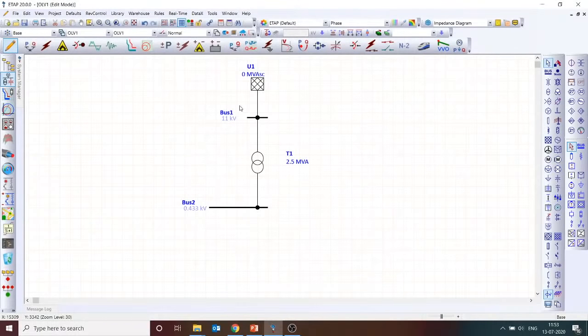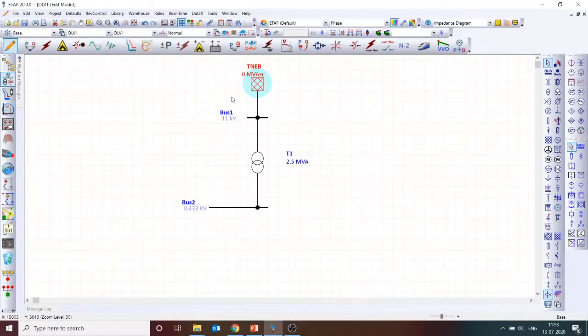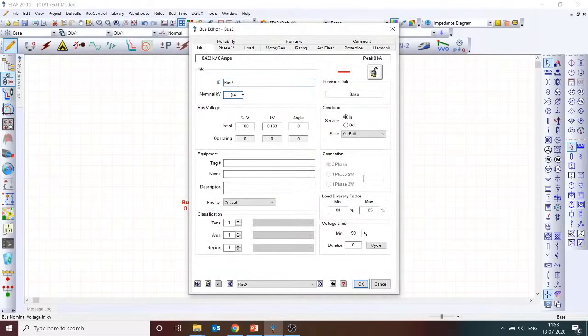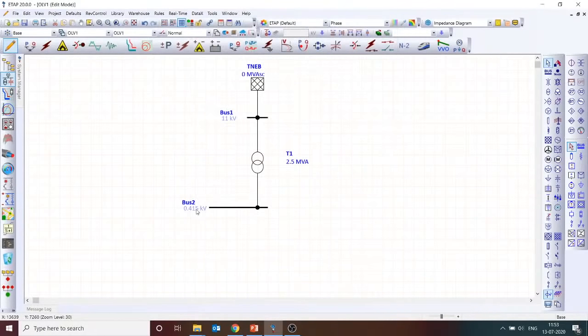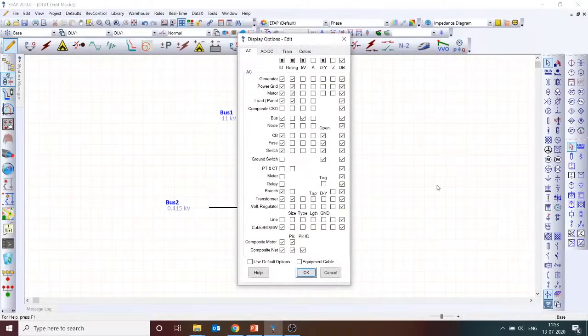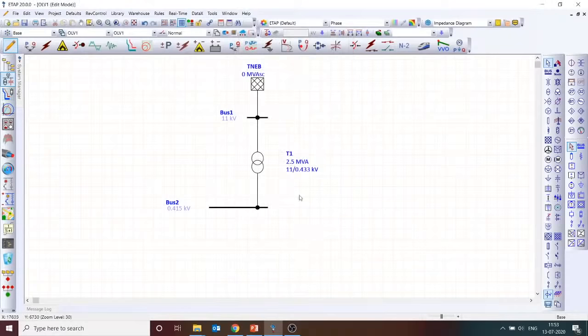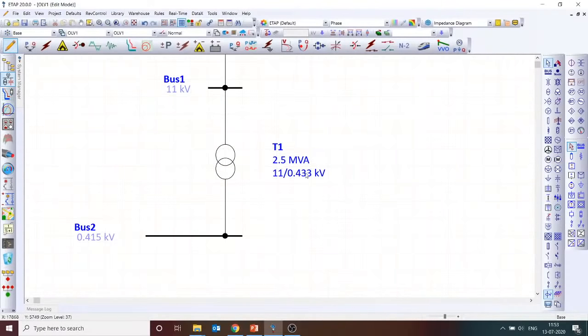So what I have done now: the industry receives the power supply from the electricity board, say TNEB in Tamil Nadu, or TANGEDCO, at 11 kV, and using their 2.5 MVA transformer, they step down to 415 volt. But interestingly, I have intentionally added one specific piece of information. The bus voltage is 415, but the transformer voltage is not 415, it is 0.433. If you have noticed that, yes, that's perfect. HV side is 11 kV, LV side is not 415 volt, it is 0.433.